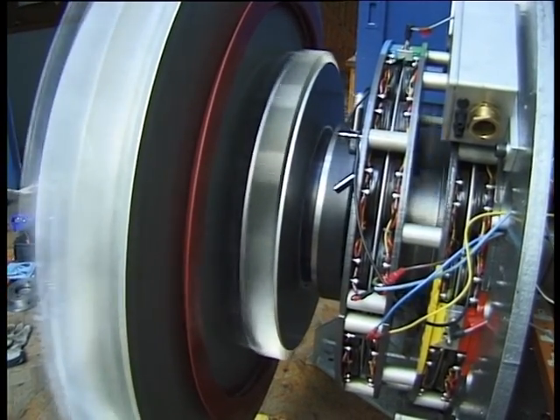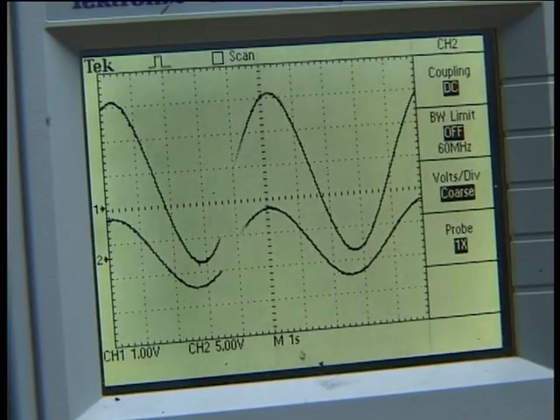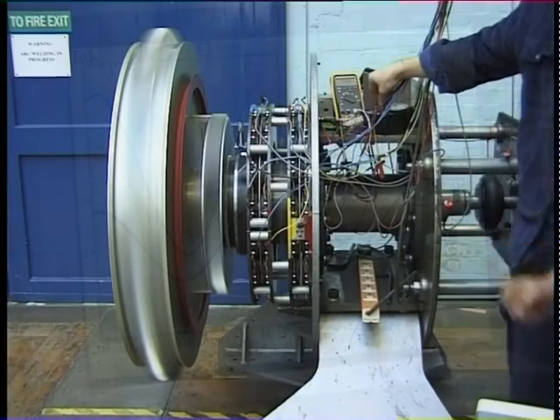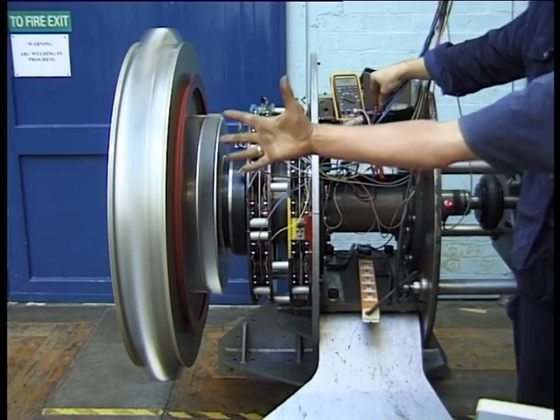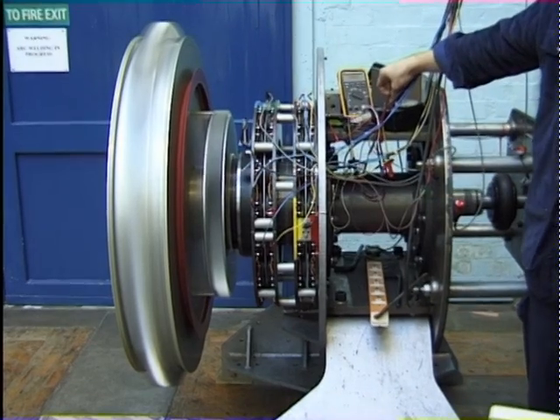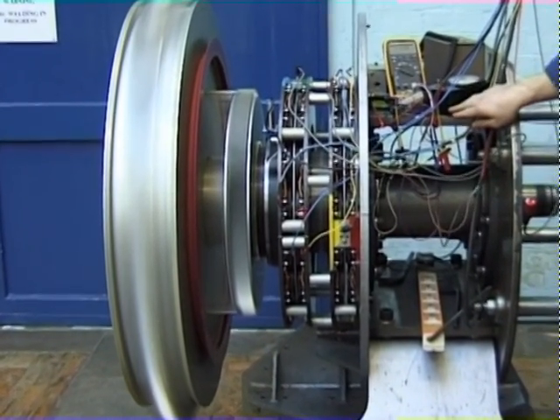This was during the final 1999 full speed pitching test, with all of the instrumentation in place. At 1500 rpm the turbine is spinning at its nominal speed. The actuator is running through full pitching cycles faster than should ever be required for the Azores waves.